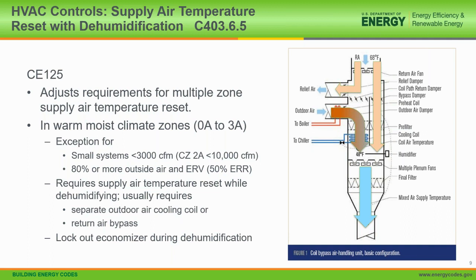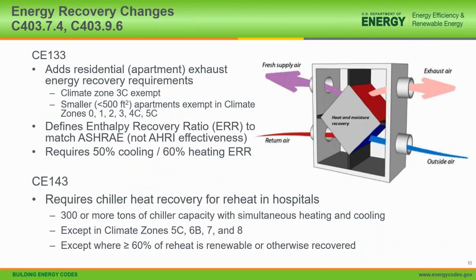And there's also a requirement there to lock out the economizer during dehumidification so that we aren't bringing in excessive outside air. That probably makes sense, but not everyone was doing it, so that control requirement got added to the code. CE 133, and these are both related to energy recovery.